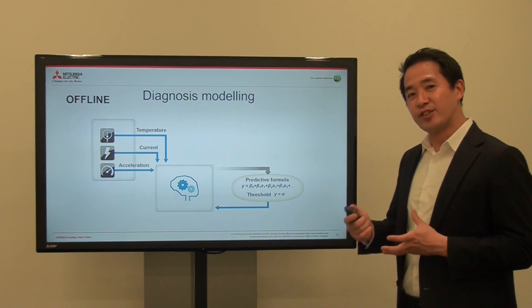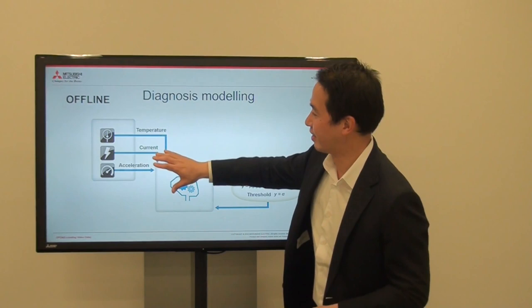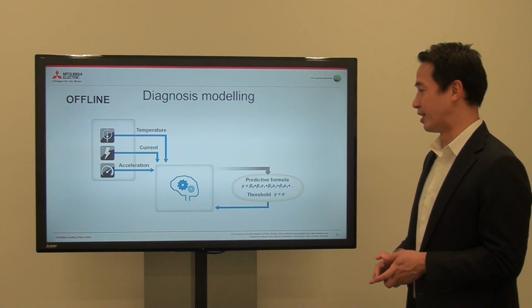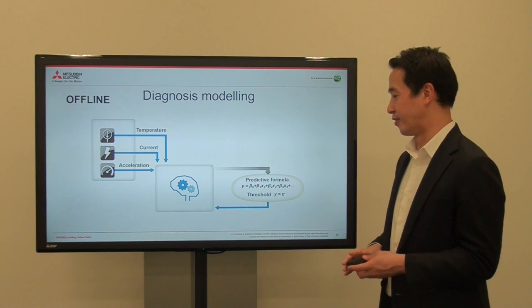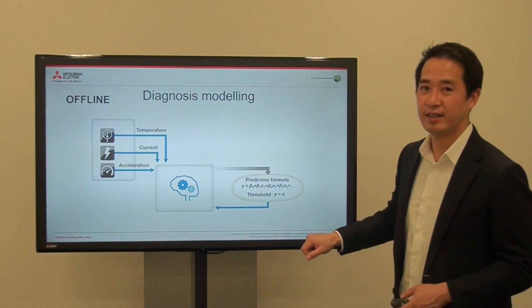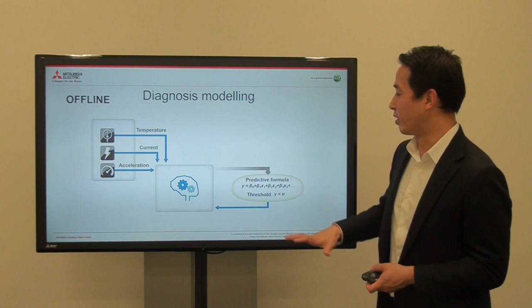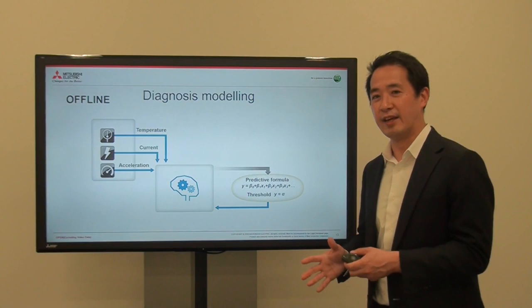After doing the data diagnostics, we found out that the temperature, current, and acceleration patterns of the motor were most relevant to the gear wear. So we took these three data points and made a predictive formula: temperature is A, current is B, acceleration is C — with some multipliers — and we will be able to determine the gear wear. We also create a threshold.